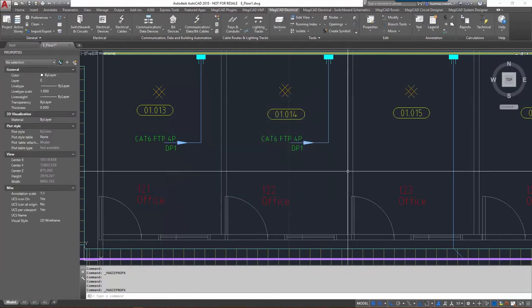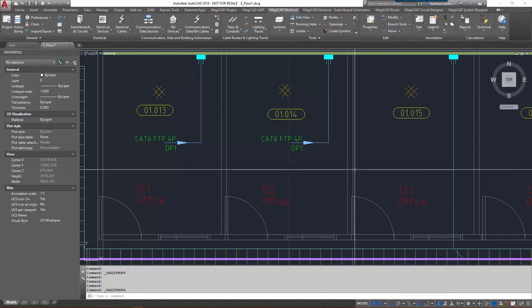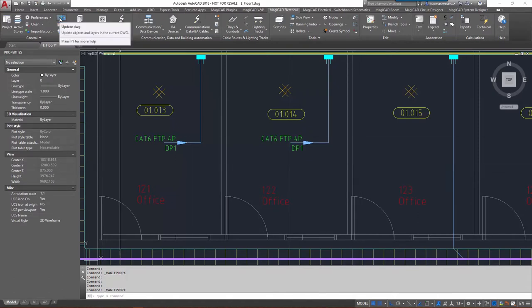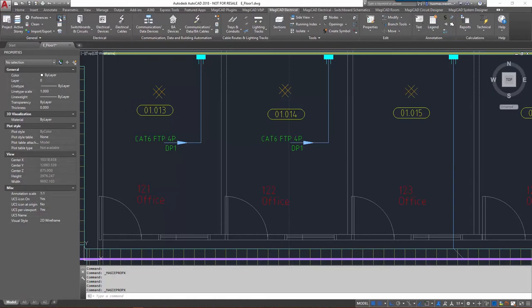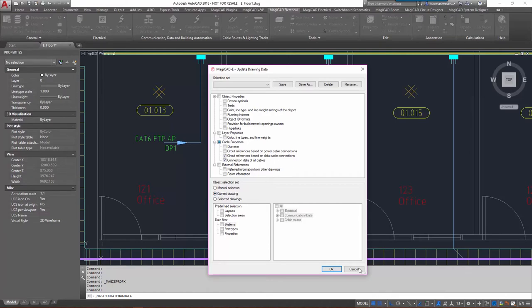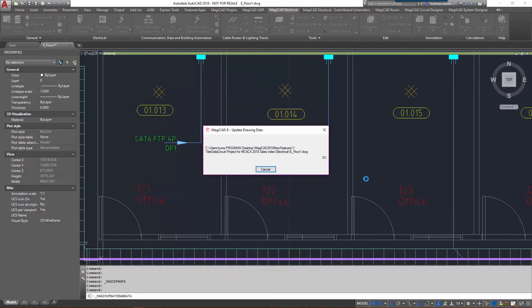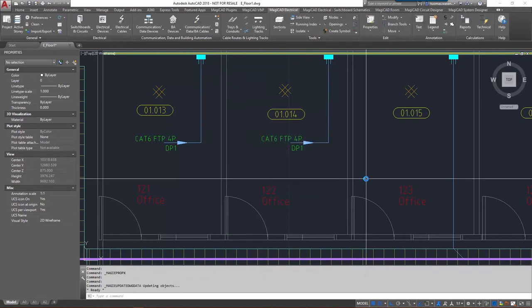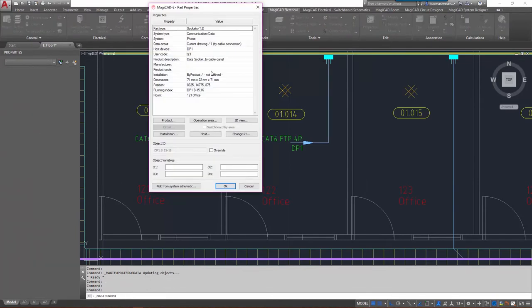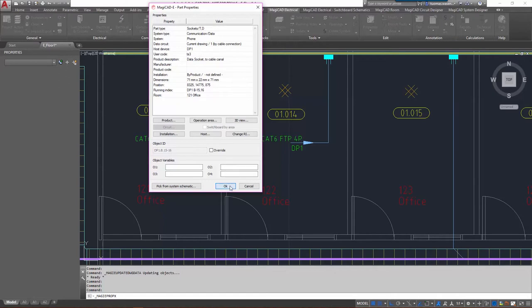So now that all these three devices are connected to the data panel, let's see how to actually apply these changes. I'll start with the update drawing and I'll concentrate on the cable properties here. So I'm going to update circuit references based on data cable connections and the connection data of all cables, and I'm going to run it on current drawing. I'm adding the information from the circuits to the actual devices so that now they should be connected, and as we can see if I check it from one of the data sockets, the host device is set as DP1 as it should be.